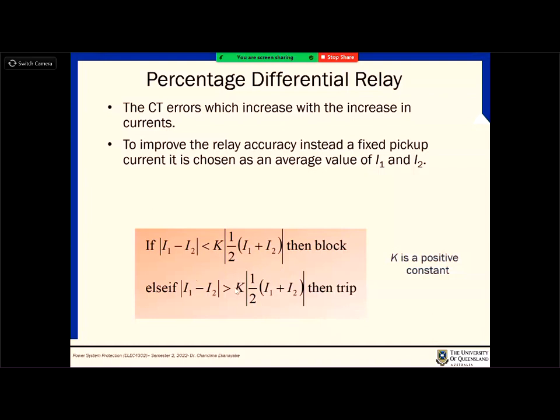See, K is a constant. You can set it to 0.1 or 0.01, whatever. But then the trip value depends on the current going in these lines. So now, when the current goes up, your pickup setting is increasing. When the current goes down, the pickup setting decreases. So now, you are always looking at a certain percentage of the total current going through the system. That makes sense in a way, because you are not operating it for unnecessary conditions, and you can also operate it for all the required conditions. So that's why the percentage differential relay is the more practical one, right?